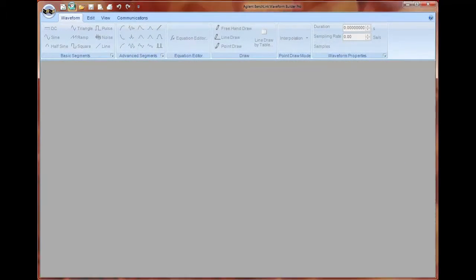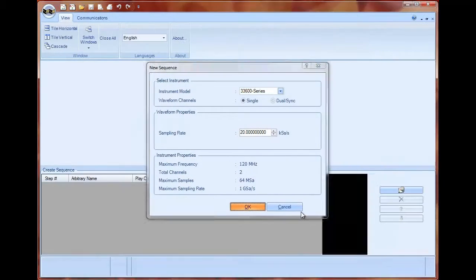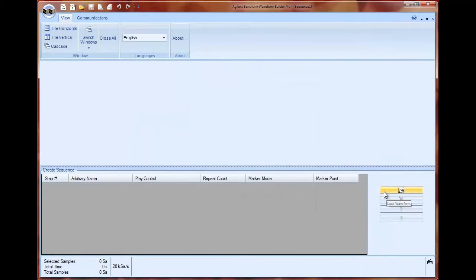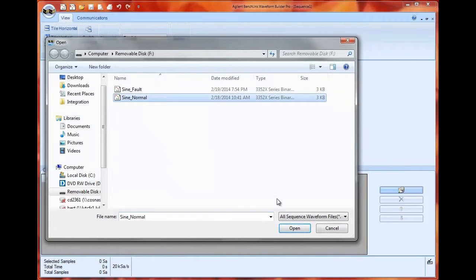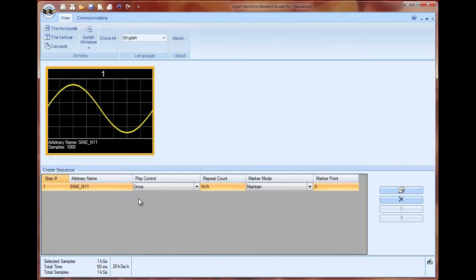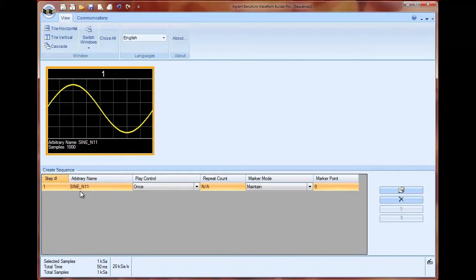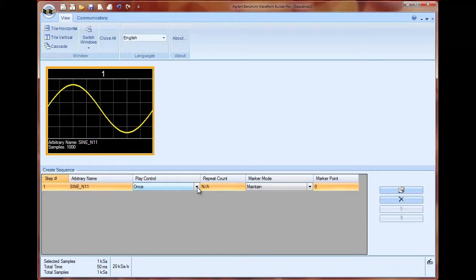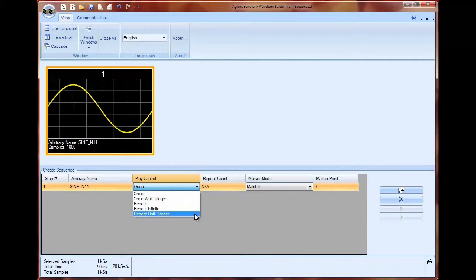I have a couple of arb waveforms that I've created to perform dropout testing on the bench. The first one I am going to open is just a normal sine wave and once I load that into the BenchLink Waveform Builder Pro software I can control how I want to set up my sequence. This is going to be the first arb in my sequence and I want to go ahead and play this arbitrary waveform until a trigger is received.